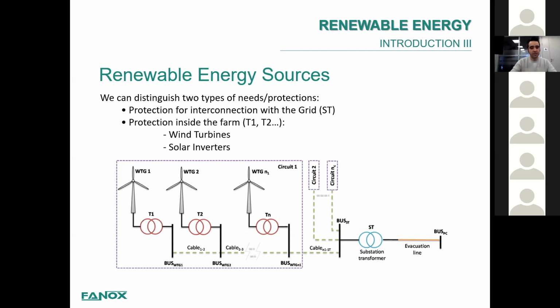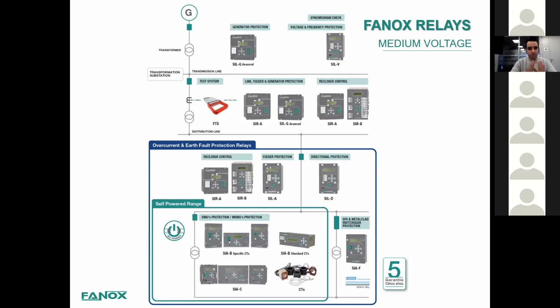So what you can see on the slide is the transformers T1, T2, T3, Tn that are inside the wind turbines or the solar inverters. Here we can see, just to show you, a portfolio of Fanox. We have products for all the steps of energy production, but in this presentation, we're going to focus on the overcurrent and earth fault relays. As I said, this is going to be for the protections inside the wind farms. And specifically, we are going to talk about self-power relays that we think can give us something much more and advantages regarding traditional relays on this kind of connections.